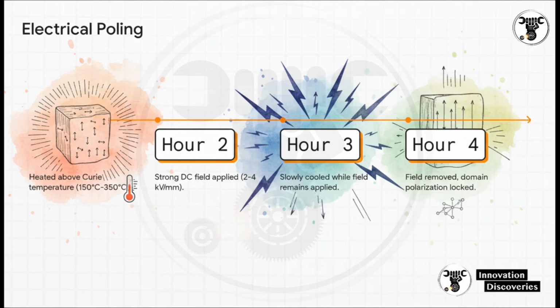First, we heat it way above its Curie temperature, somewhere between 150 and 350 degrees Celsius. Then, bam, we hit it with a massive DC voltage, talking up to 4 kilovolts per millimeter. As it slowly cools down, that electrical polarization gets permanently locked right into the crystal lattice. Now it's active. Now it can actually generate a signal.